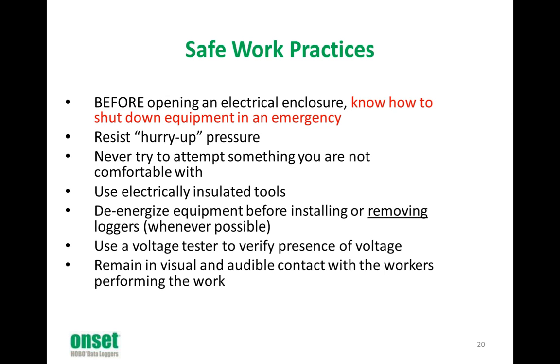Before we open an electrical enclosure, know how to shut it down in the event of an emergency. Always resist hurry-up pressure, take your time, and never try to attempt something you are not comfortable with. Use electrically insulated tools. De-energize the equipment before installing or removing data loggers. Obviously, that's whenever possible, because you would need equipment energized while taking voltage readings. Use a voltage tester to verify the presence of dangerous voltages, and remain in visual and audible contact with the workers performing the work. So it's always good to have at least teams of 2.